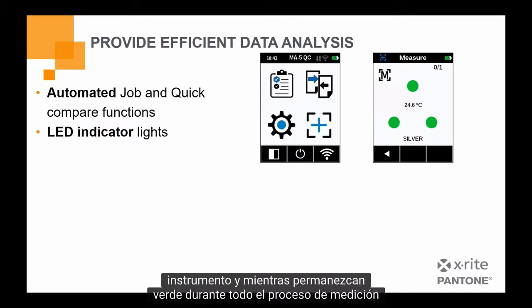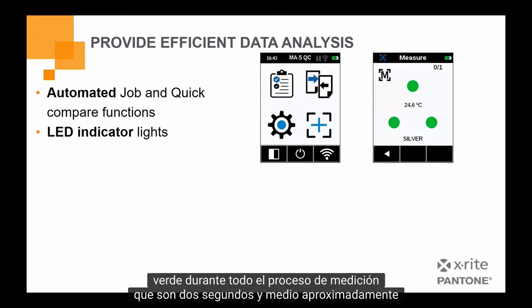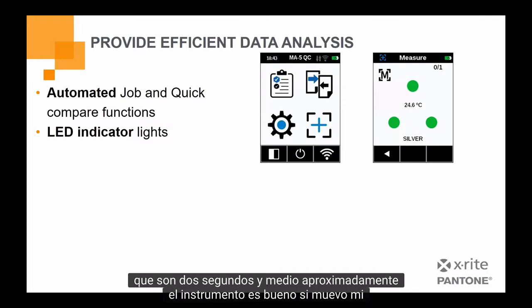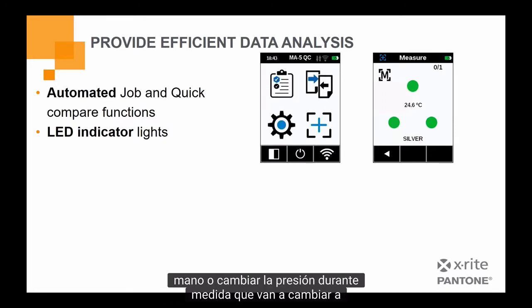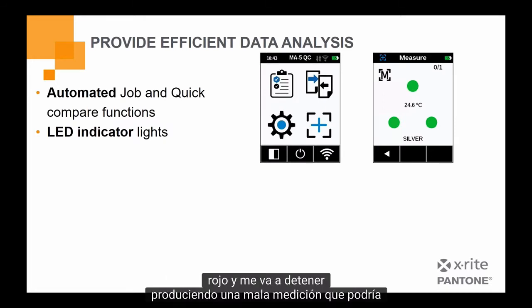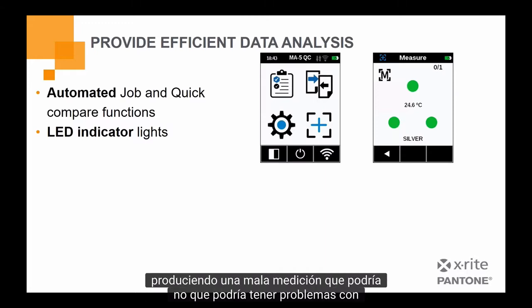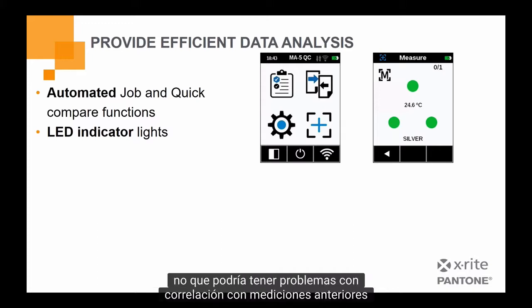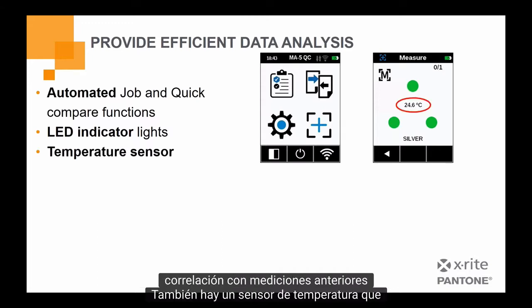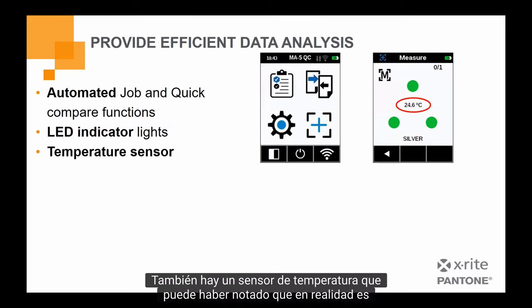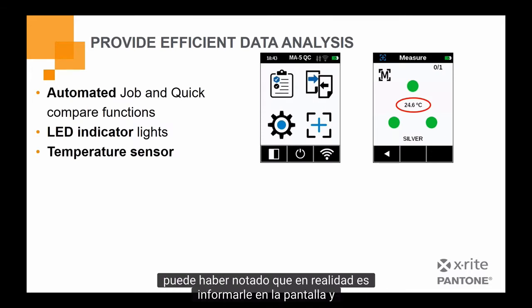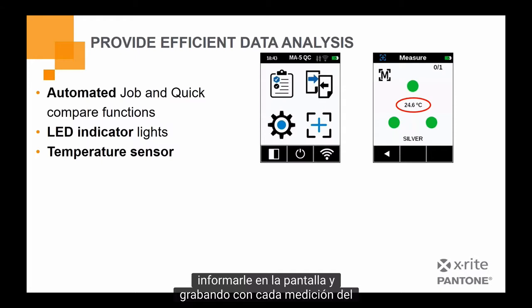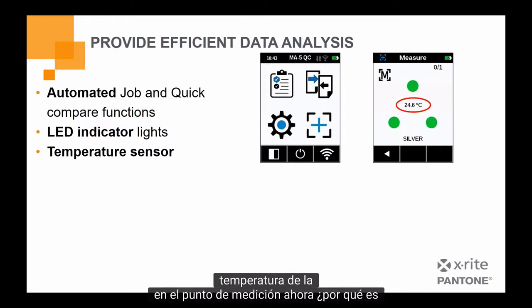And as long as they remain green throughout the measurement process, which is 2.5 seconds roughly, the instrument is good. Should I move my hand or change the pressure during measurement, they're going to switch to red, and it's going to stop me from producing a poor measurement, which could have issues with correlation to previous measurements. There's also a temperature sensor. You may have noticed that. It's actually reporting to you on the screen and recording with every measurement the temperature at the point of measurement.